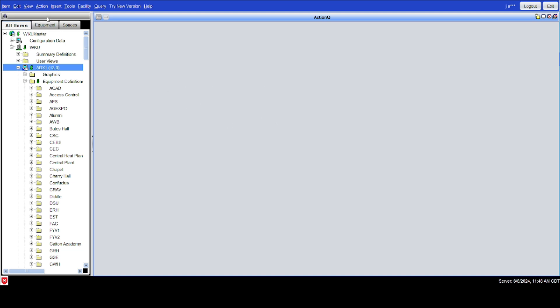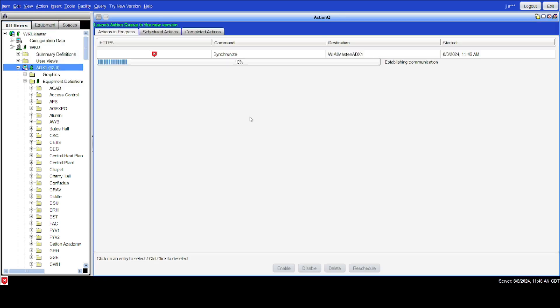Once you get all that done, the only thing you need to do is download your server — go to your manage archive and download that server, or you can do a synchronization. It really depends on your system; some earlier versions of Metasys have to do a download rather than synchronization due to a glitch on certain versions. Once you download that server and get everything working, those points will populate within your system and you can add them from your aliased equipment object into your graphic. Thanks for watching — leave any questions down below, check out the rest of the videos on my channel, and we'll see you next time.